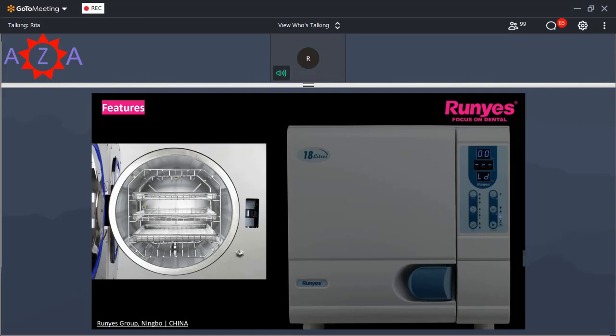One more important component I want to highlight is we install a steam spray barrier at the back side of the chamber. This is one important upgrade we did 2 years ago. You should know that the function of this barrier is to distribute the steam going into the instruments uniformly, which can reach much better sterilization for instruments. Okay, so this is the chamber.